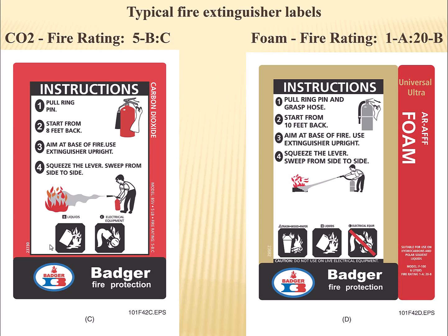And you see it's got a rating of 5 for B, and it's rated for C also. So it's only good for B and C. It's not rated for A. Now actually it's not particularly dangerous for class A fires, but it's not effective on them. Because carbon dioxide doesn't hang around as a gas, it's good at snuffing out a liquid fire. But it doesn't hang around long enough to do anything more than a momentary removal of the flame for a class A fire.